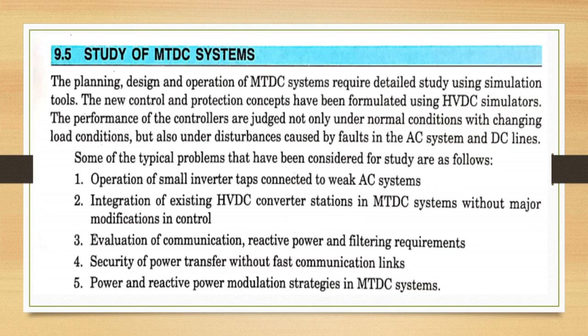Some of the conclusions from studies carried out indicate the type of problems that can be anticipated in the operation of MTDC systems connected to weak AC systems. Let us see the first one. A large smoothing reactor may be required to help in the recovery of a small inverter from AC faults. Second one will be the speed of recovery of the entire MTDC system depends upon the recovery of the small tap if it is still connected to the system following clearance of a fault.